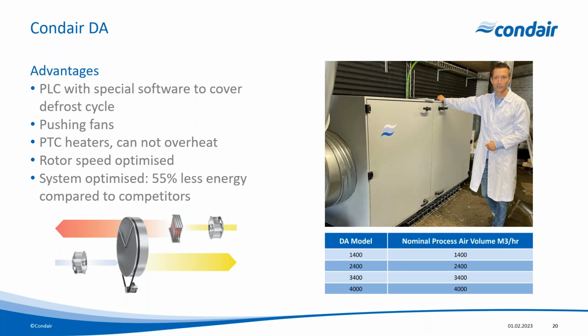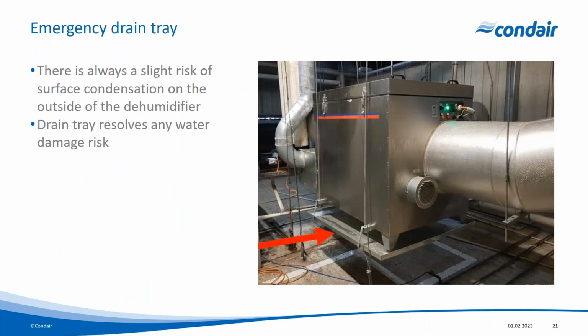So it's really critical to consider the sizing and the selection of the unit to make sure that we're matching those fan speeds, rotation speed, and regeneration heat as accurately as we can. So here you can see a picture of a dehumidifier, and this is mounted above the cold store. And you can see that we've got 100 mil thick insulation of the air that's coming from the cold store. So it's coming out of the cold store here, running through the dehumidifier and then out again. And then this duct here is your regeneration air that's being taken from ambient. In this case, it's above the cold store. It's going through the dehumidifier and then out and being vented out to external.